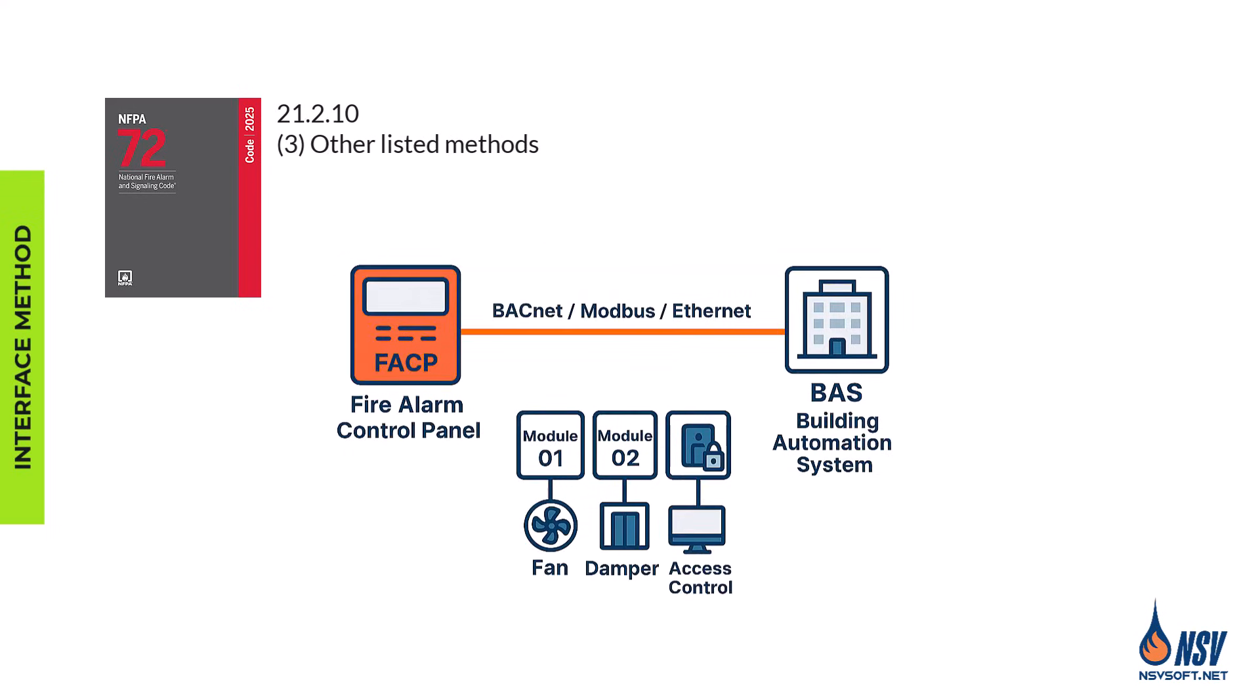The third method is communication protocols. More sophisticated integration uses network protocols like BACnet or Modbus, which allow for intelligent two-way exchange of data and commands between the FACP and building automation systems over a common network infrastructure.